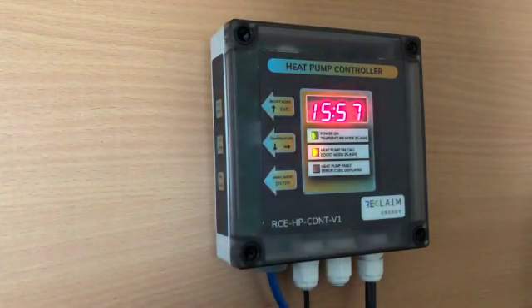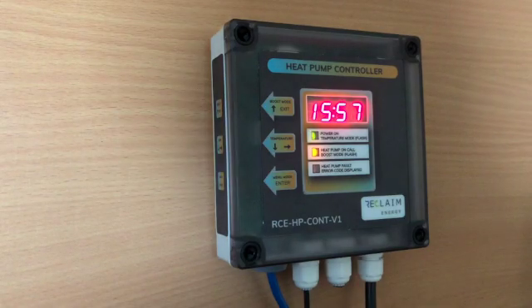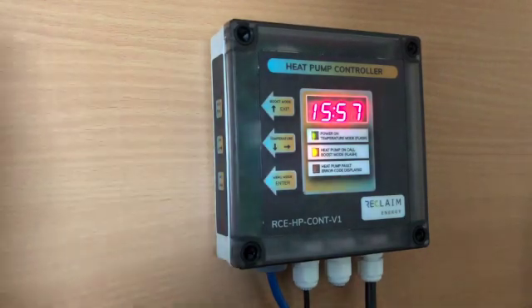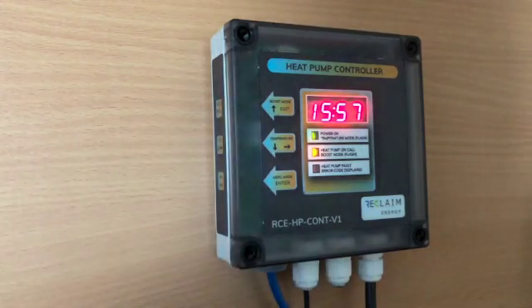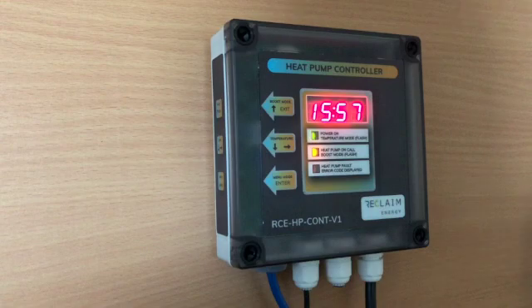Now each of them correlate to a different time period. So for example, like we said, option one is a 24 hour mode. That means that there is basically always a call for heat. So if your tank temperature drops below a certain level, then that heat pump will come on.